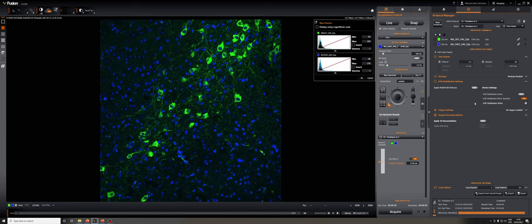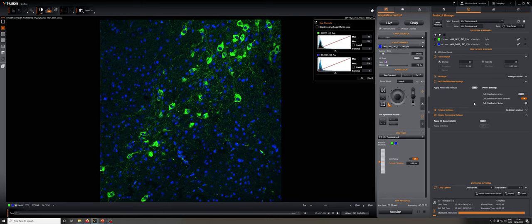The way the system measures the distance between the front of the objective and the sample is by measuring a reflection that occurs as a result of the difference between the refractive index of the immersion media and some part of the sample. So the system works very well with air objectives, because there's a large difference in refractive index between air and the cover glass.